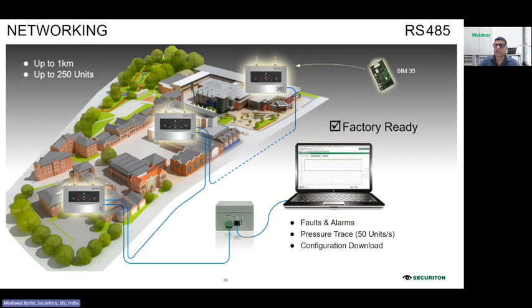If you talk about networking, RS485 networking is possible. You can go up to 1 kilometer without a repeater, up to 8,500 with repeaters, and you can have five repeaters per network if you have a bigger system. Up to 250 ADW control units can be networked, and they can be monitored with the help of the software tool, which is available on your screen, and a lot of different values can be seen live.